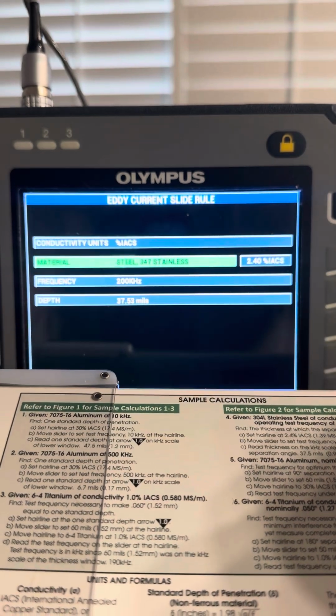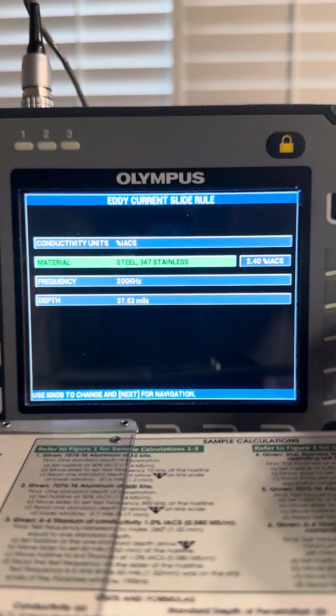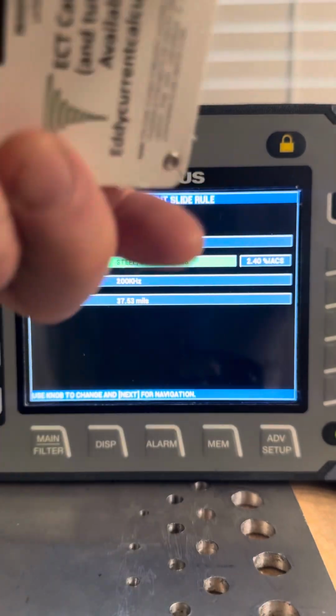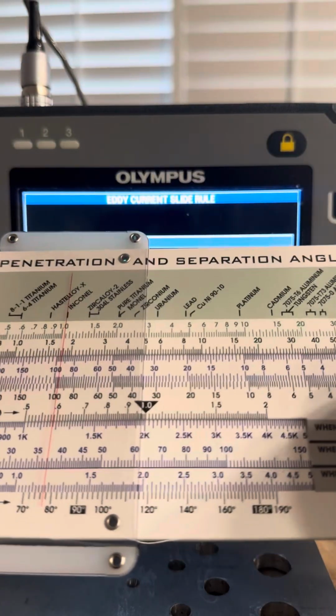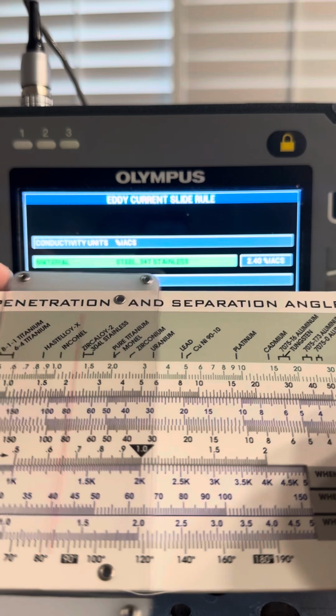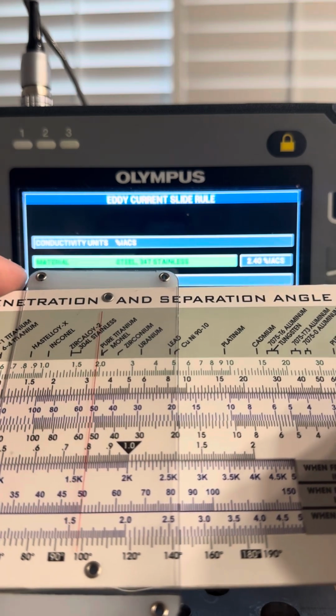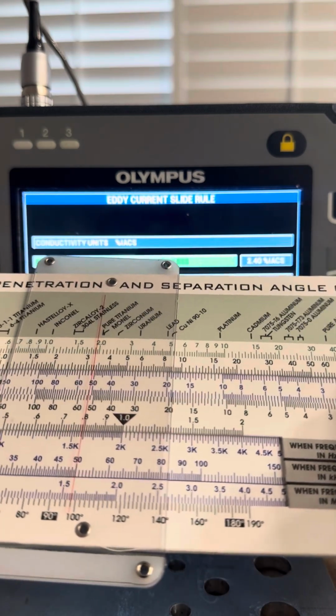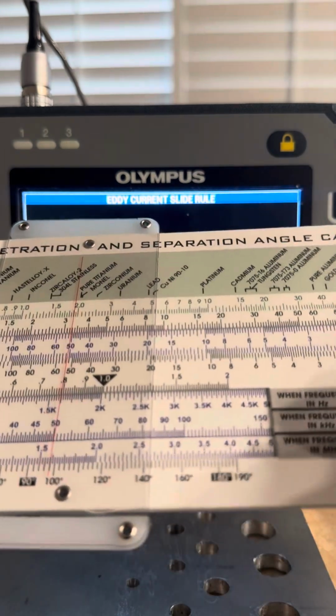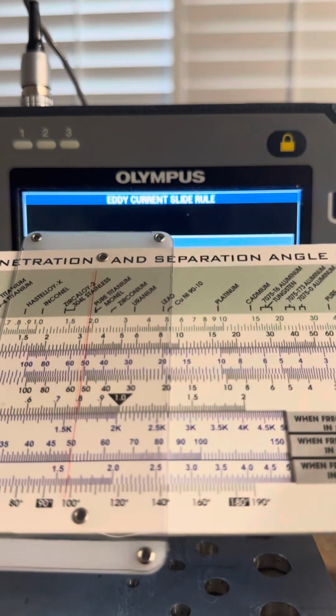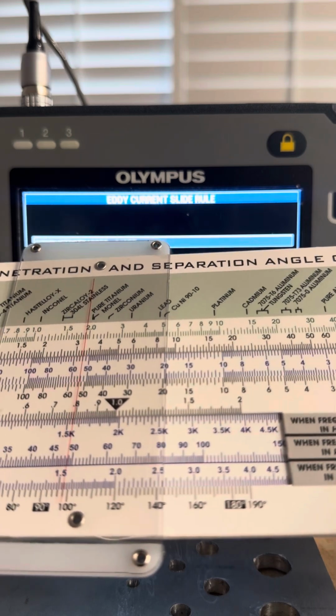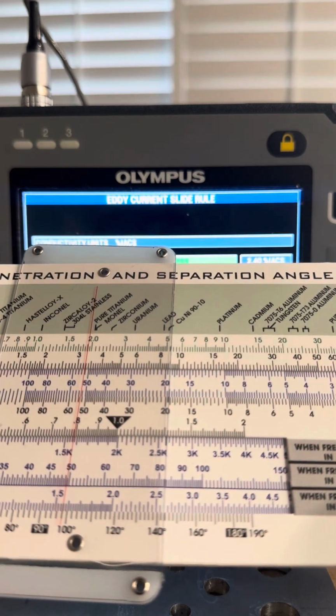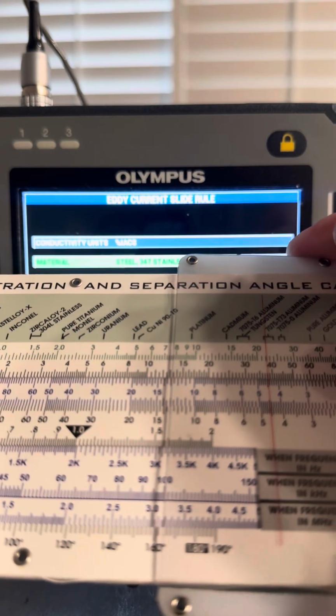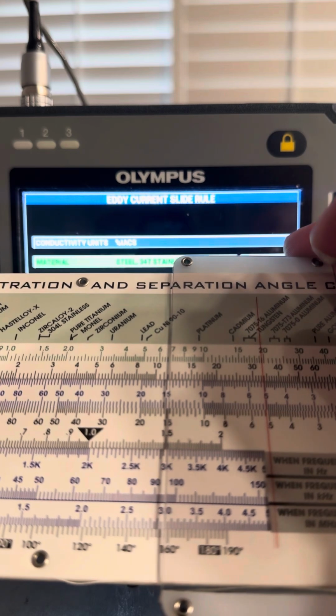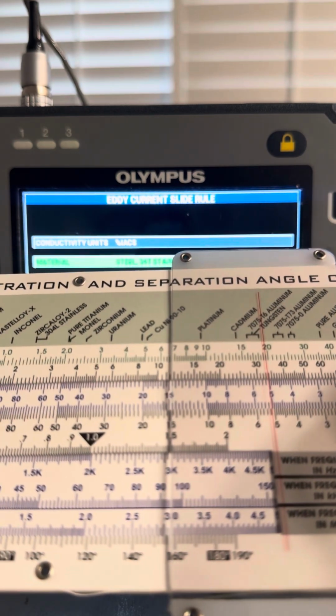Another thing is calculating F90. That's not an option on the 600D. But when you have the slide rule, all you do to calculate F90 for surface, you just put this red hairline to 0.8, and then you put your material right under it. We're going to use kilohertz. That's the middle scale here. So if we said 0.8 at 50 mils for tungsten, let's say, right there, 5 kilohertz would give you F90.